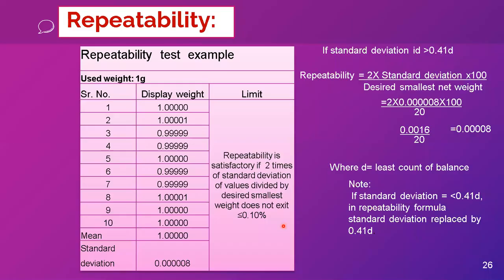For repeatability in performance qualification, the same method applies as discussed earlier: take 10 values, calculate the standard deviation. If standard deviation is greater than 0.41D, use the standard deviation in the formula; if less than or equal to 0.41D, substitute 0.41D. This completes the repeatability test in performance qualification.